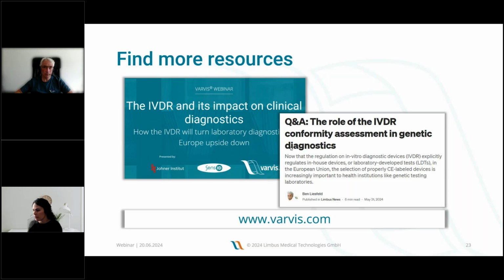So we have one question now, which is, why can manufacturers choose a device classification that does not make sense? Yeah, a good question. And I'm not sure if I have an answer for all classifications. The IVDR is structured so that it's the responsibility of the manufacturer to determine the classification.